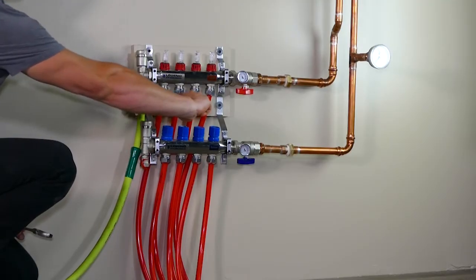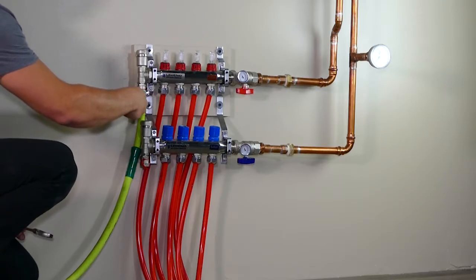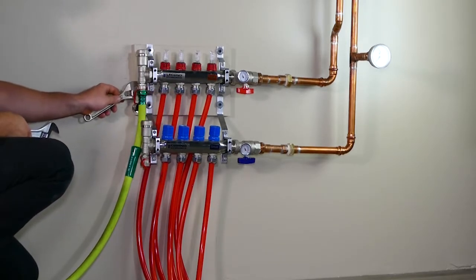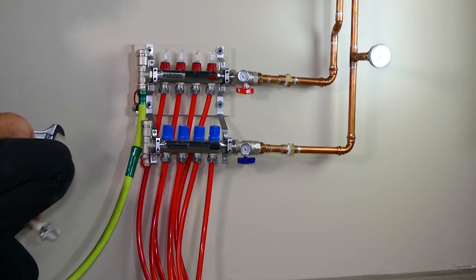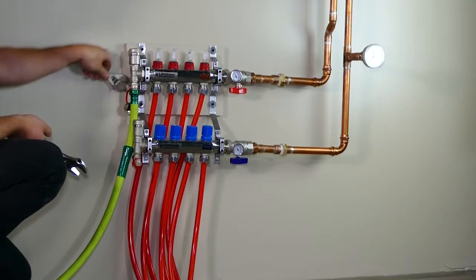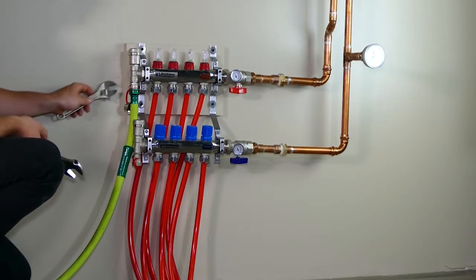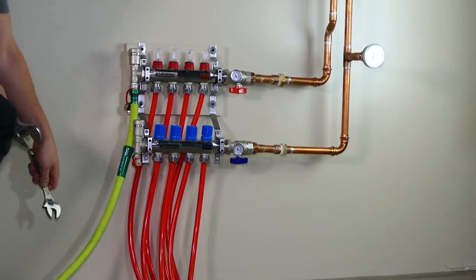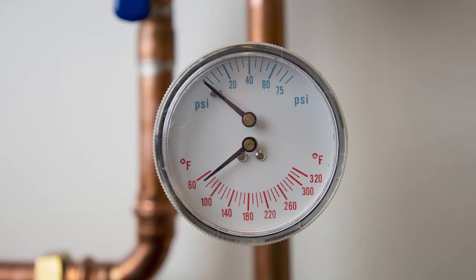Once you are ready, it's time to fill and purge the loops and boiler. If you're using a propylene glycol solution, remember to not use more than a 50% ratio. Using propylene glycol can lower your BTU output and change the flow of the circulator pump. You will need a minimum of 7 psi in a system for a boiler to operate. Typically, hydronic systems require a psi above the pre-charge expansion tank. For the NextGen boiler, that is 14 psi.